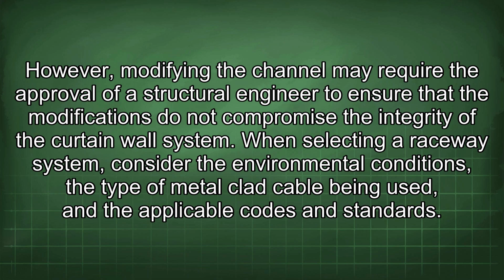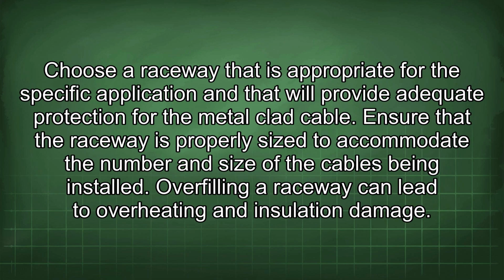When selecting a raceway system, consider the environmental conditions, the type of metal-clad cable being used, and the applicable codes and standards. Choose a raceway that is appropriate for the specific application and that will provide adequate protection for the metal-clad cable. Ensure that the raceway is properly sized to accommodate the number and size of the cables being installed. Overfilling a raceway can lead to overheating and insulation damage.